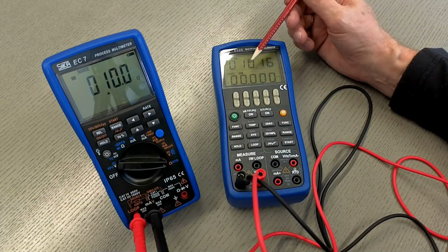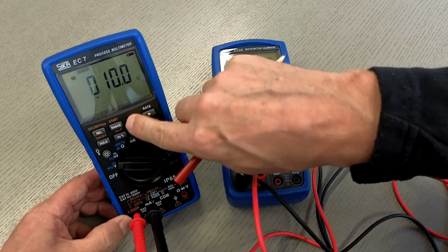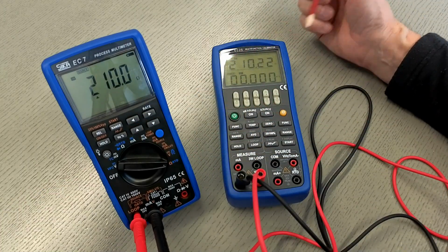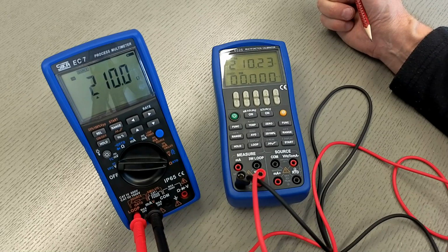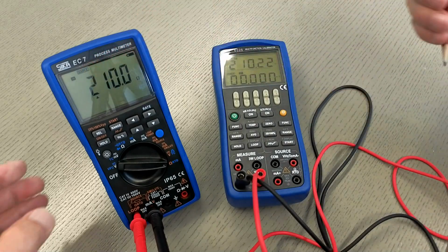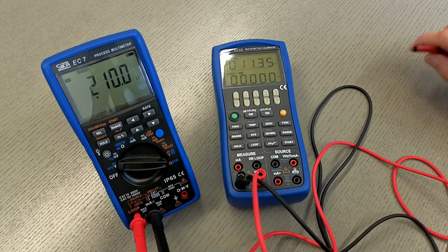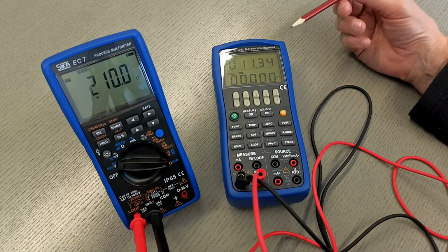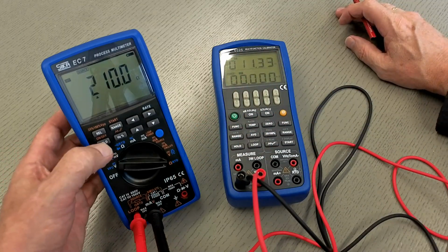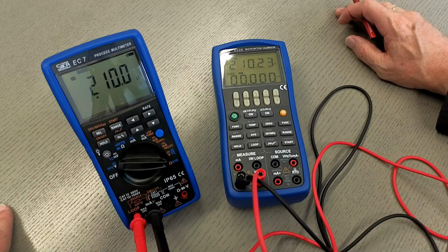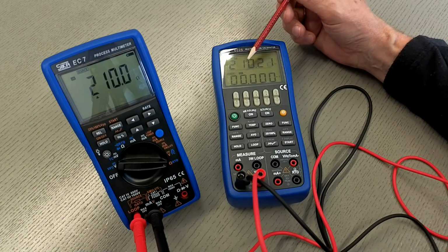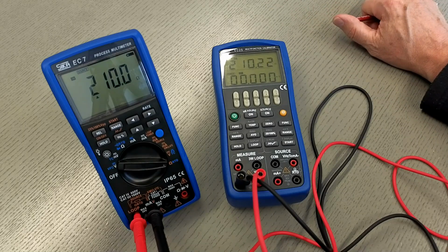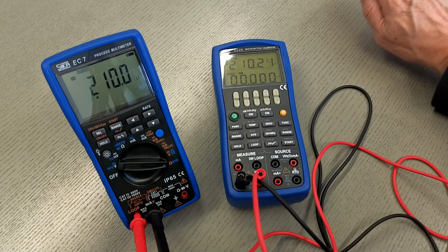So I switch over to, for example, 10 ohms. I see 10 ohms. I switch over to 210 ohm. So that means then I see 210 ohm. It's switched on. It's switched off. By switching off, I see the value of the wires, including the electronics. And so I switch it on again, and I see again the 210.23 ohms. So everything is within the right value.